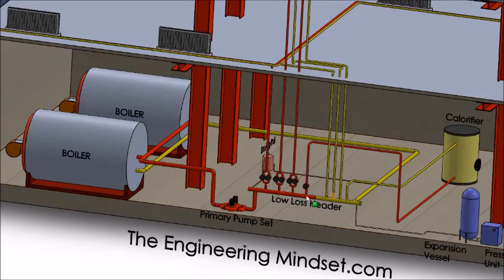And coming off of the header from the hot side is these, which are risers, and these go off and these make up the secondary circuits. So in this example we've got 4 secondary circuits, 1, 2, 3 and 4. Some of them have got this dual pump, and this one has got a single pump. It may not need a pump if it's close enough and the primary pumps are actually powerful enough, but in most cases you will have a pump on this in this configuration.